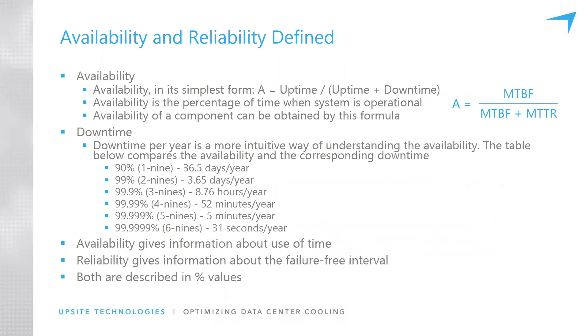A more detailed definition: availability in its very simplest form is uptime divided by uptime plus downtime — how long a system is up — and it's always expressed as a percentage. In terms of meantime between failures and meantime to recovery: MTBF is meantime between failure.